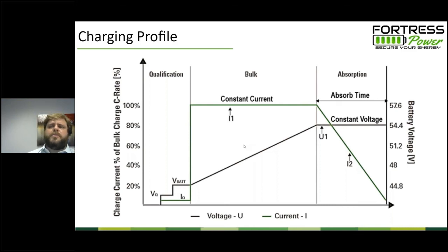And so when you're programming your inverter settings with our batteries, it's very common to disable the float and just say we're going to do a bulk and absorb charge but no float. Well, some battery inverters won't let you disable the float. We don't use an equalization charge on a sealed battery.